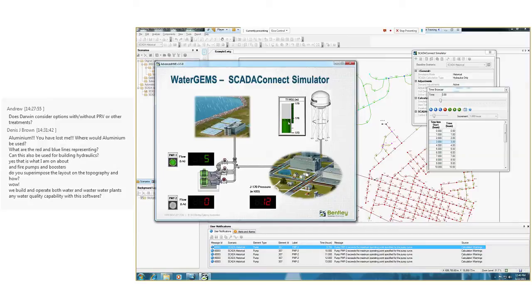And this time, you see the tank drains, pump 1 turns on, the tank continues to drain, and then pump 2 comes on this time.